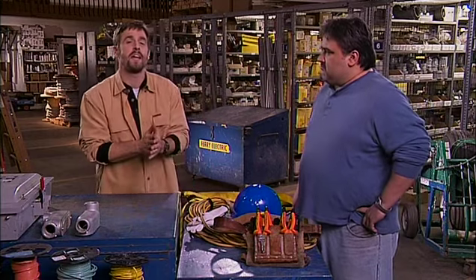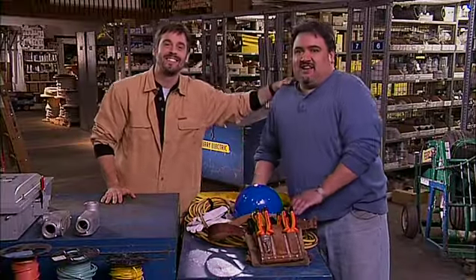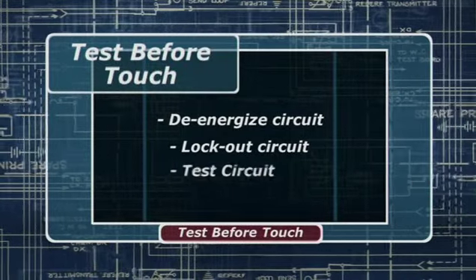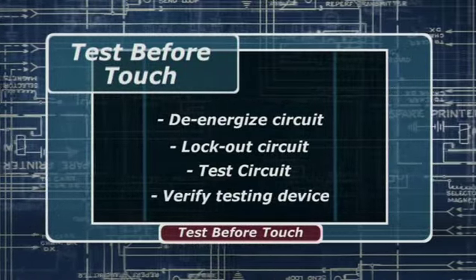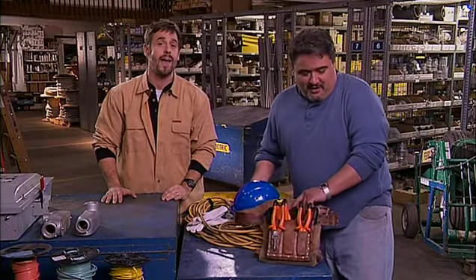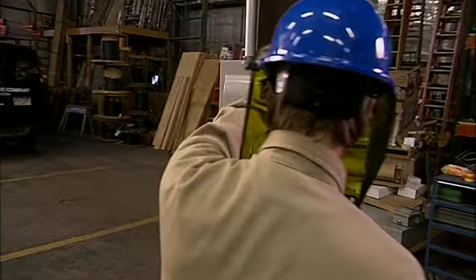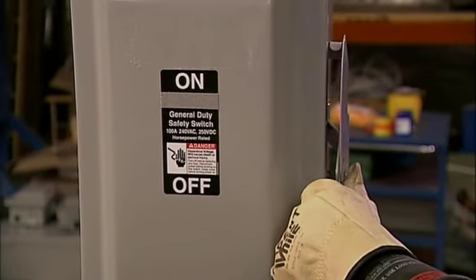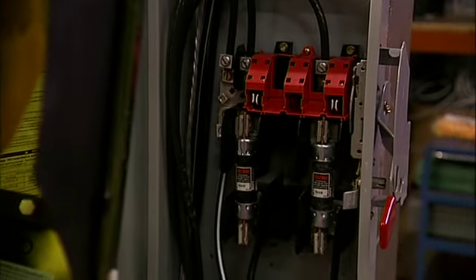Okay, let's get to the test before you touch. I know the mantra. Every person tests every conductor every time for absence of current before they touch it. Very nice. Thank you. Okay, off to work. No, wait a minute. You're not done just yet. There's de-energize the circuit, lock out the circuit, test the circuit, and verify the testing device. Case closed, the end. And before you get started, you slip on your voltage-rated gloves. It's an OSHA mandate. And you de-energize the circuit by determining all possible sources of electrical supply to that specific piece of equipment that you're working on.